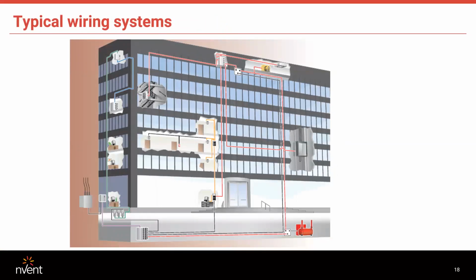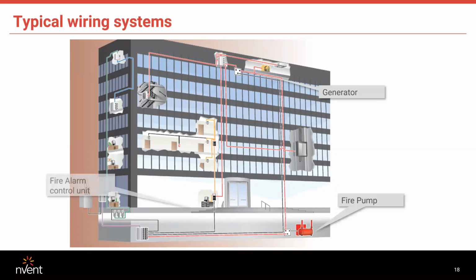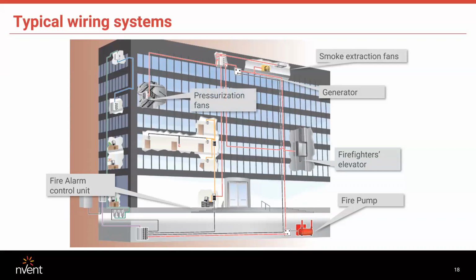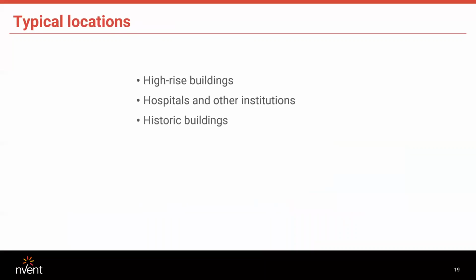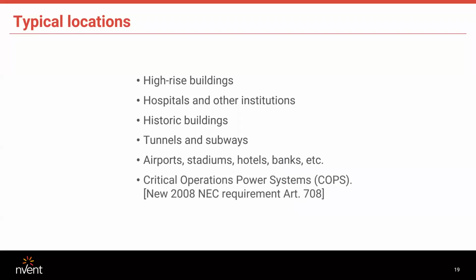Now, where do you typically see the need for fire-rated wiring? Of course, a generator, fire pump, fire alarm control unit, firefighters' elevators, smoke extraction fans, and pressurization fans. Typical locations: high-rise buildings, hospitals, other institutions, historic buildings, tunnels, subways, airports, stadiums, hotels. As I mentioned, also critical operations power systems.